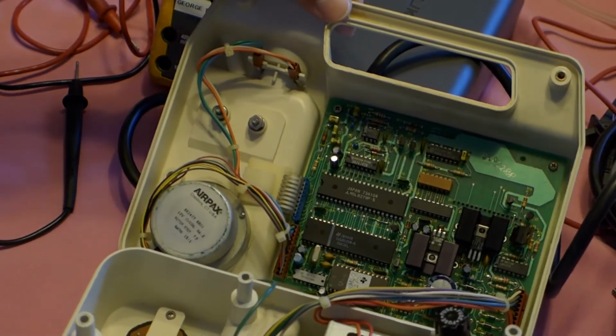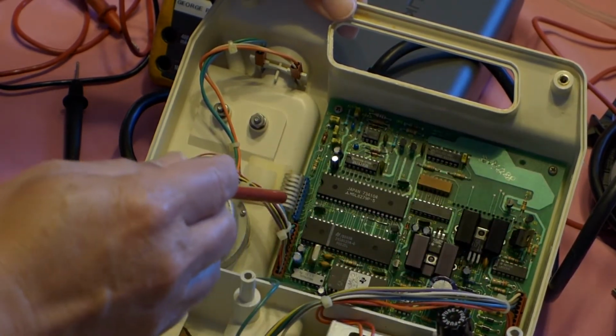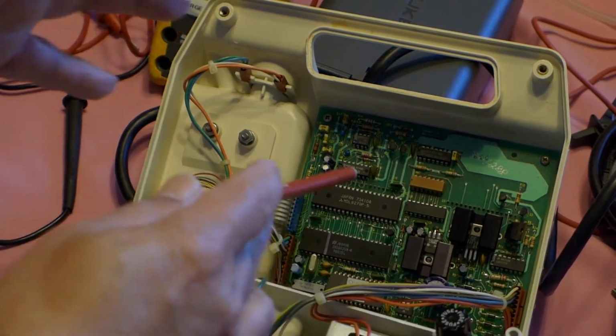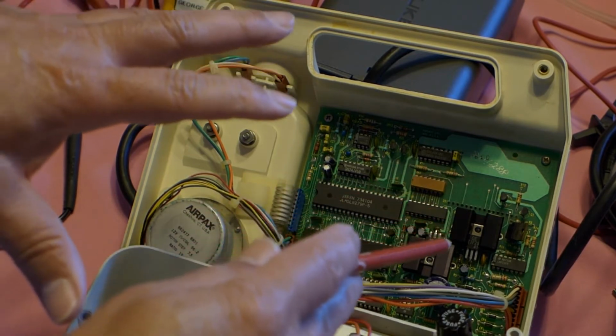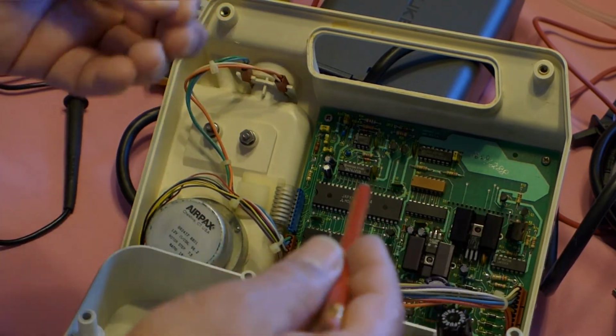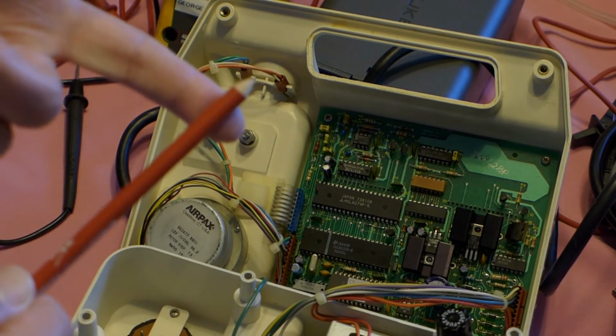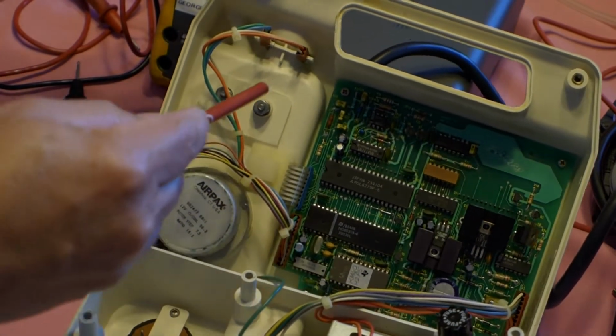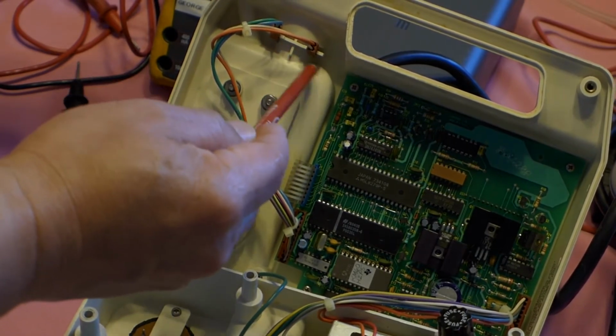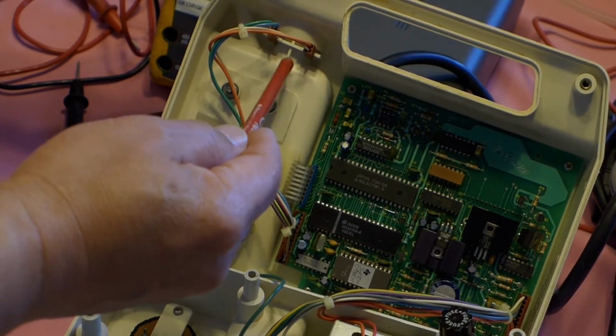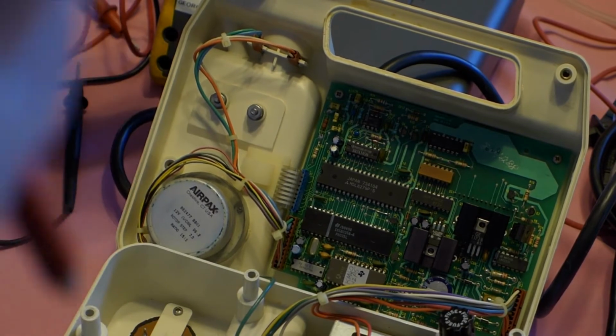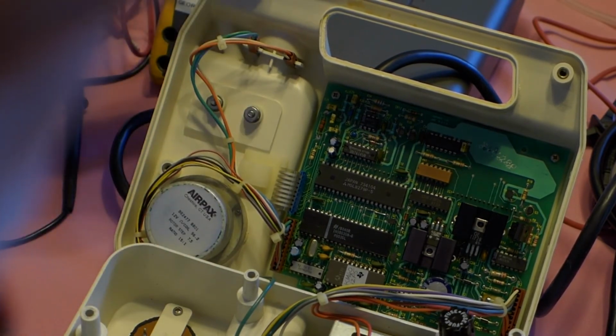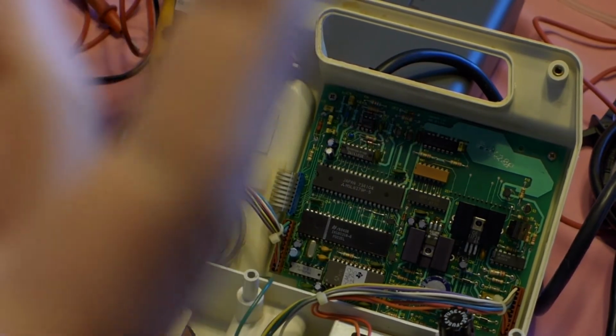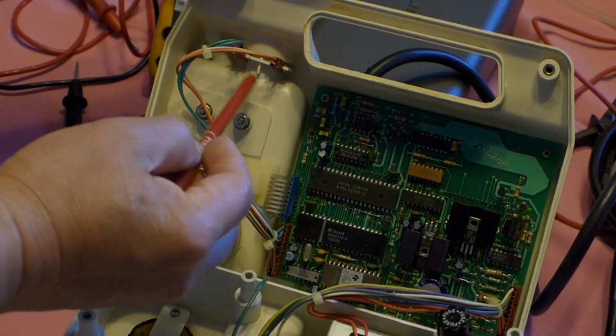Now let's look at this part of the pump. Here you have a stepper motor. We have a processor, and this processor is used for programming the volumes and the rate, and also provides the display and alarms. When the volume is complete, or when occlusions occur, it will go into alarm. Also, there's a sensor over here. We call this a drip sensor. The function of the drip sensor is to detect the droplets of the fluid. So if the fluid stops, it will give us an alarm, saying the volume is complete, something like that. So this is the drip sensor here up in the front.